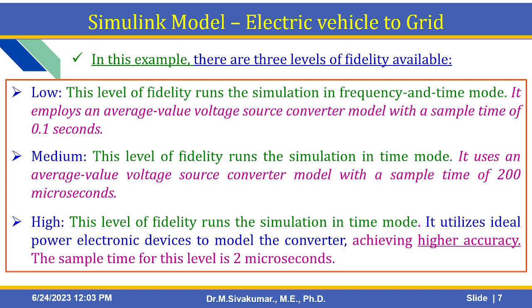Another concept is fidelity, with three levels available: low, medium, and high. Low fidelity runs the simulation in frequency and time mode, employing an average value voltage source converter model with a sample time of 0.1 seconds. The medium fidelity level runs the simulation in time mode using an average value voltage source converter model with a sample time of 200 microseconds. The high fidelity level also runs in time mode, utilizing ideal power electronic devices to model the converter for higher accuracy, with a sample time of 2 microseconds.